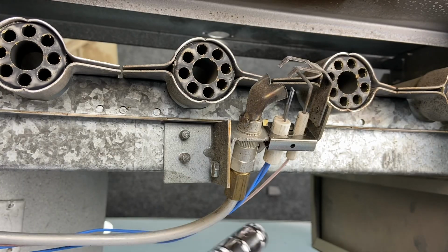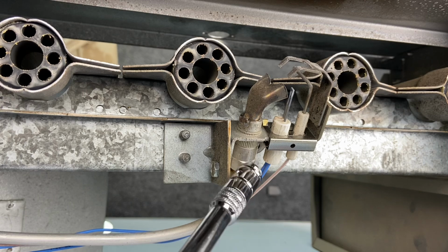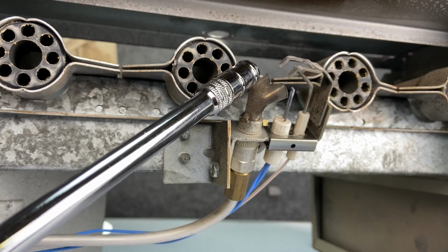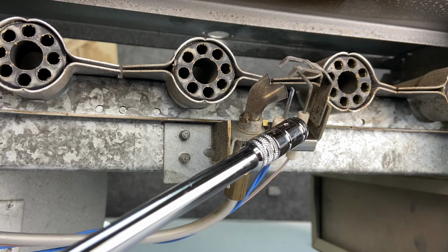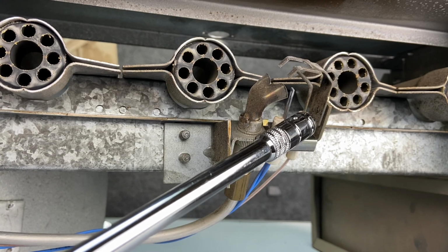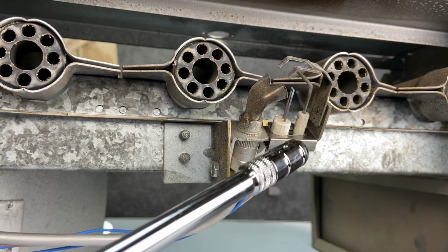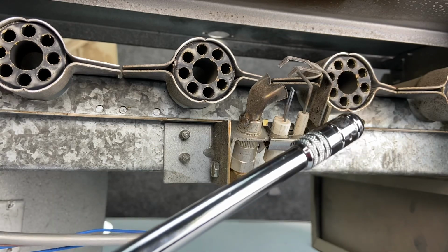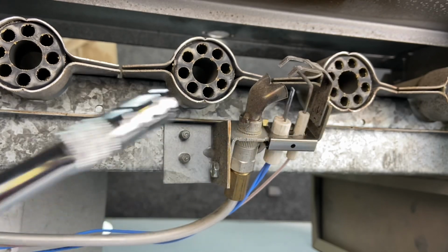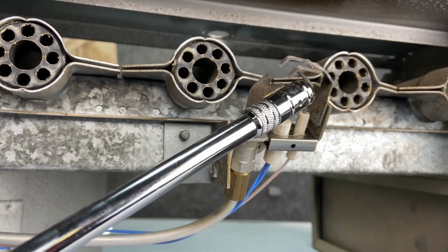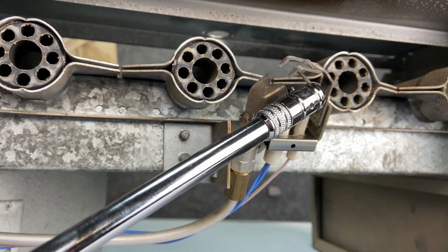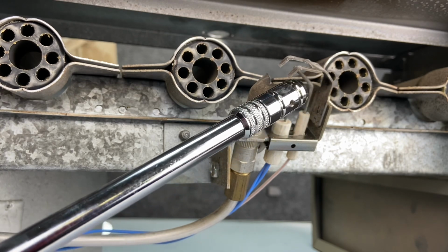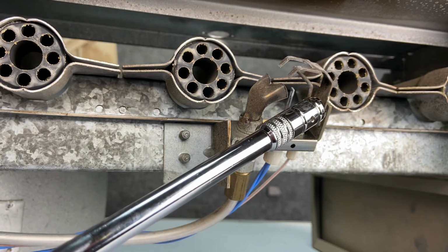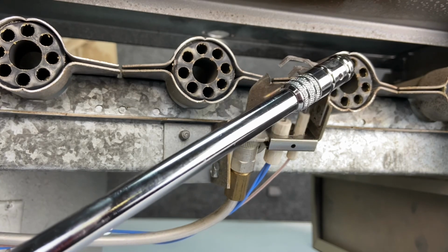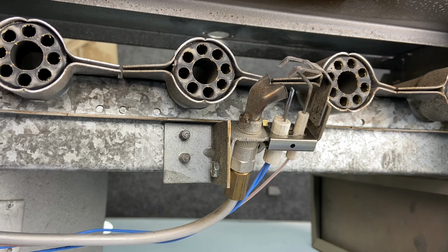Here we have our pilot tube. Inside of here is going to be an orifice just for the pilot, and this is the pilot burner. It directs how that flame is going to burn. Right here is our miniature hot surface igniter, and right here, this little bitty rod is our flame sensor. It's our miniature flame sensor, and then this is our ground part here. So when the pilot's burning, it's burning across that flame sensor, and that allows flame rectification. In other words, the flame becomes a switch, and as the flame conducts electricity through this rod to the ground, it makes a pulsating DC signal that's quite unique that the control board reads.